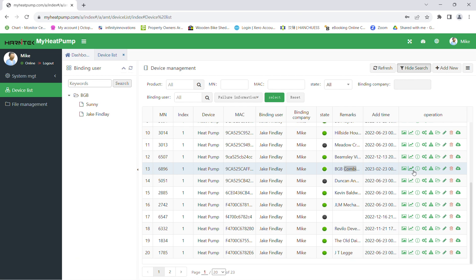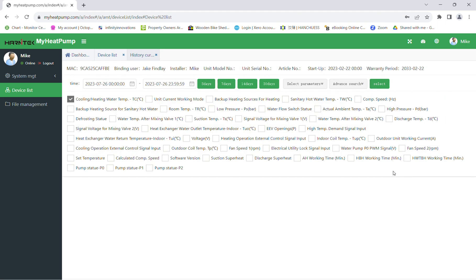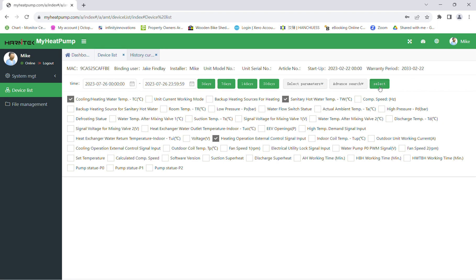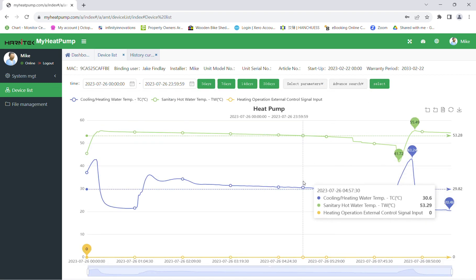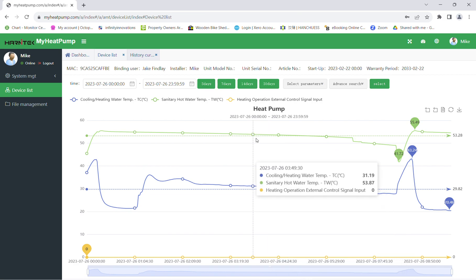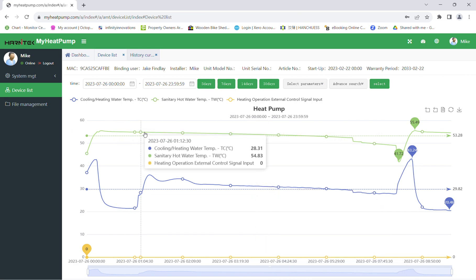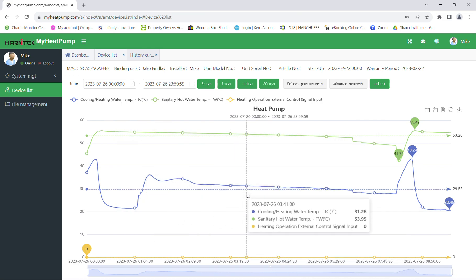The next available option is looking at the parameters of how that heat pump's been running, so you can optimize this system should you require it. We can look at cooling and heating water temperature, sanitary hot water temperature, and as an example, if there's a third party room stat installed on this system, you can also look if that's permanently been running and if it's just to do with the programming of that. If we look at those, it brings up exactly how that system's been running and gives you a key at the top so you know exactly what you're looking at.